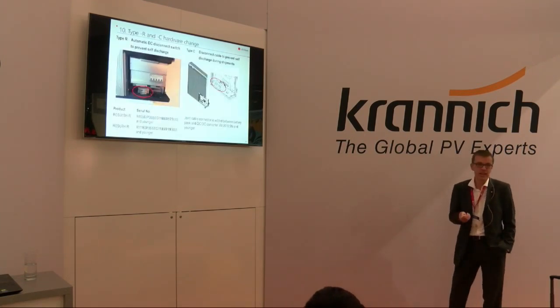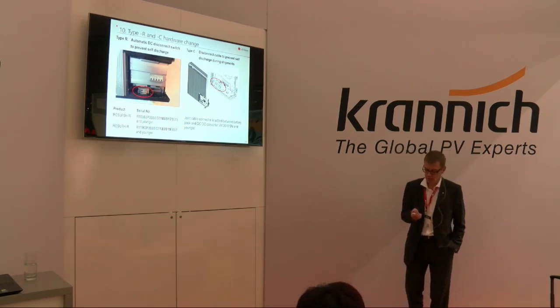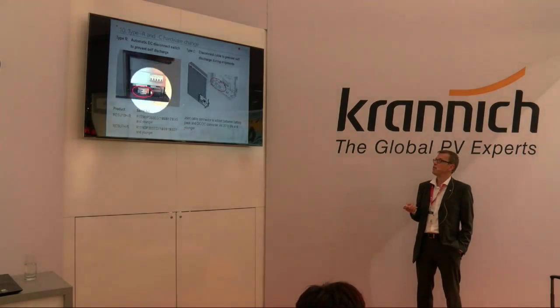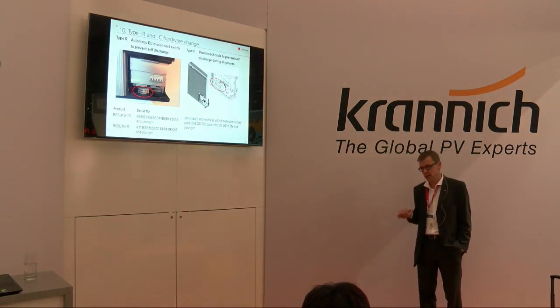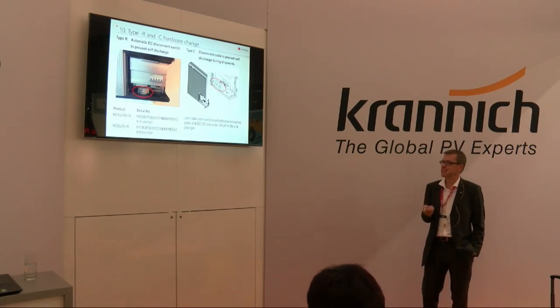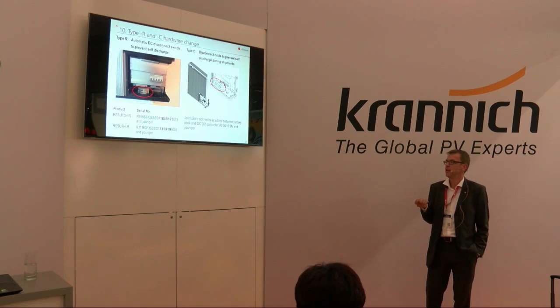Another hardware change I would like to talk about is that we have changed the converter of the high voltage batteries. There is now, for the R-type product, an automatic switch which replaces the aux switch, which was available in the last 2 years. This means the converter is fully automated now, and in case of any battery error, of any inverter error, the automatic switch disconnects the battery pack from the converter, which means there won't be any discharge in the future anymore. The same for the Type C product.